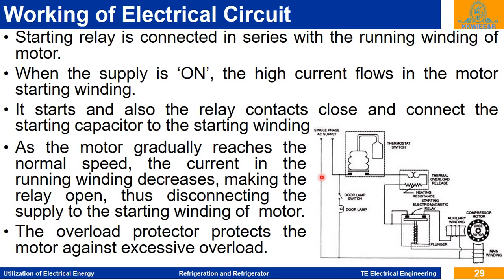So this is the thermal overload relay used in the refrigerator. This relay basically has a bimetallic disc or bimetallic strips. When excessive current flows in the motor, this current also flows through the bimetallic disc, and its temperature increases, and it opens the circuit automatically to stop the motor. A bimetallic strip has two different metals with different temperature coefficients, so the strip starts bending and disconnects the current path or supply to the single phase motor.